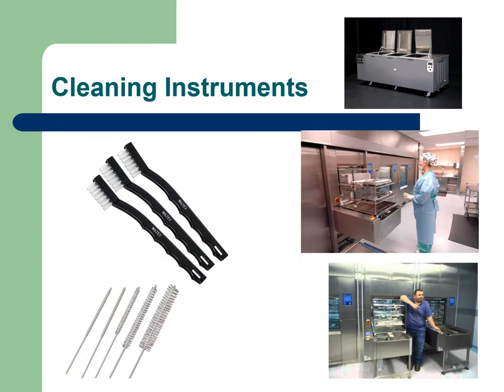When they're doing the cleaning, they'll probably start with some sort of hand cleaning. They have big sinks filled with water and enzymatic cleaner, and they put the instruments in there, especially ortho instruments or grossly contaminated ones. They soak them in the enzymatic cleaner for about 10 minutes in some warm water, making sure it doesn't get too hot - if temperatures are hotter than 140 degrees, that could deactivate the enzymatic detergent. They throw the little things in there to soak, then use a variety of brushes to scrub them and get the gross debris off.